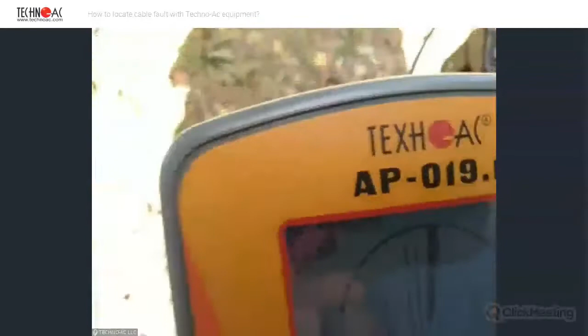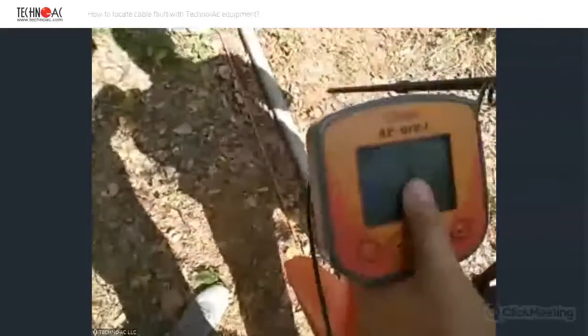You see the signal increased a little bit, but still there is no fault, there is no signal that there may be a fault. The fault will be indicated by a significant signal drop. So we have inspected 2 points, and each point had some signal. One had less, one had more. Let's approach the fault a little bit and see what will be the difference. I'm keeping a couple of meters just to save some time. And I'm placing the sensor again, and you can see on the graph here that the signal is still there. So this is the signal which is passing through the cable. And also you can check the orientation of the cable in accordance with the compass mode indication. And now we will go meter by meter, and we will check the area close to the fault.